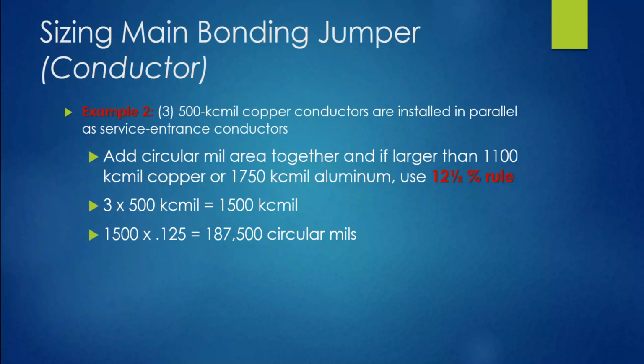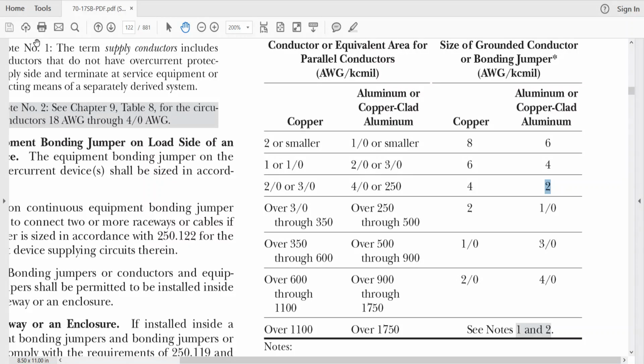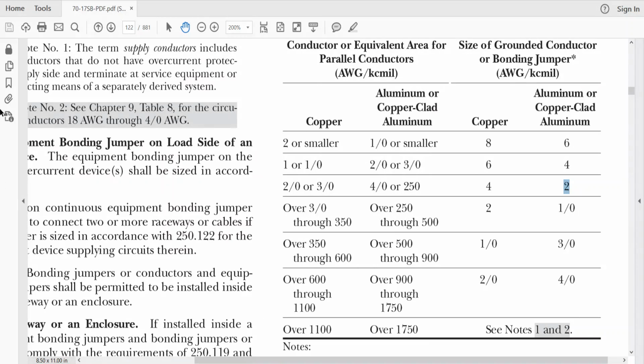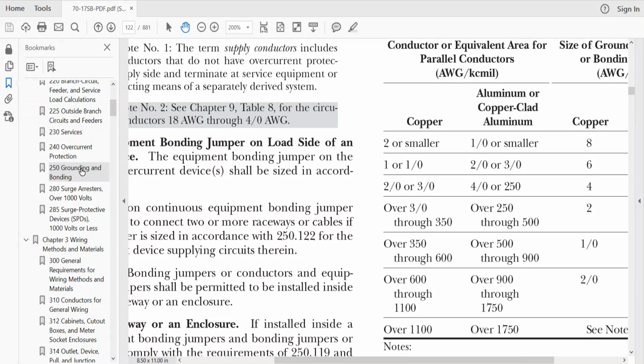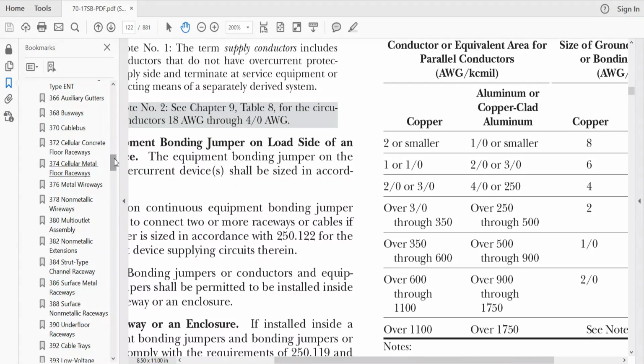Now, 1500 kcmil times what we just talked about, 12.5%, or using the decimal version, 0.125, or if you have a calculator, you can do 1500 times 12.5%, however you want to do it. And it equals 187,500 circular mils. Next thing I've got to do is go to Chapter 9, Table 8. So let's go to Chapter 9, Table 8, and let me go to the NEC. I'm going to bring this back out so that I can do that. And we're going to go to Chapter 9, Table 8.